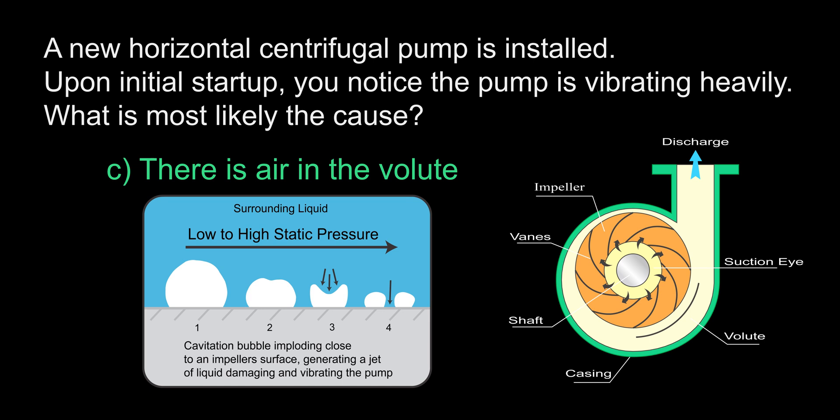To explain further, when the static pressure on the suction side of the pump becomes lower than the water's vapor pressure, bubbles form. As water is moved quickly to the discharge side of the pump, the pressure increases, collapsing the bubbles.